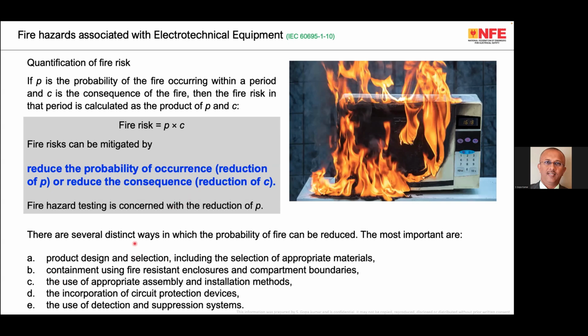The probability of occurrence can be reduced by the following factors: product design and selection, including the selection of appropriate materials; containment using fire-resistant enclosures and compartment boundaries; the use of appropriate assembly and installation methods; the incorporation of circuit protective devices; and the use of detection or suppression devices. So these are the measures which can be included to reduce the probability of occurrence.